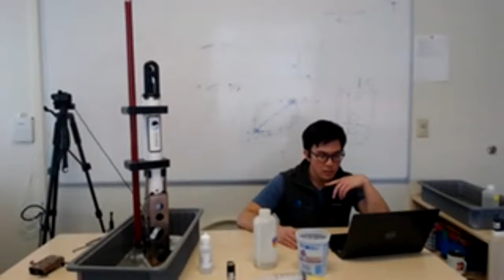No, I think mostly they're very good questions, and a lot of it is configuration dependent. So as we mentioned earlier, the HydroCAT EP has a lot of optional modular sensors that you can choose to have with your deployment setup. So a lot of the questions in terms of like the pump timeline, the sample interval, is highly dependent on what you choose to use. So the oxygen sensor, for example, flushing is recommended, and then the turbidity and chlorophyll sensor at the end of the instrument takes some time to actually open the shutter and use the biofouling wiper to actually clean the lens and then take that sample.